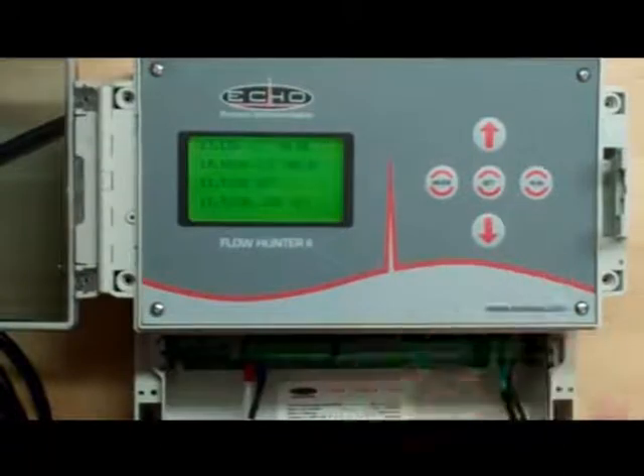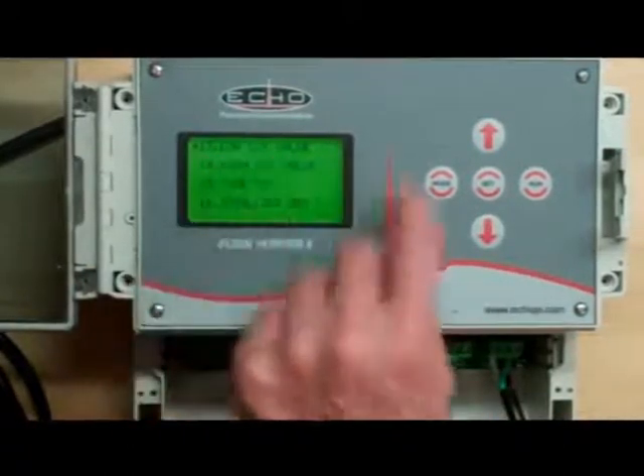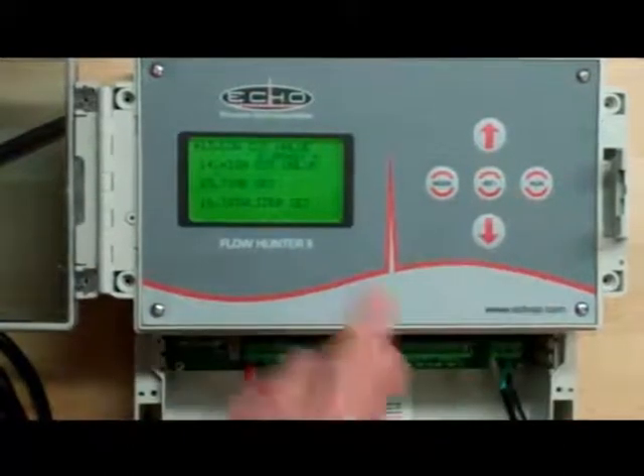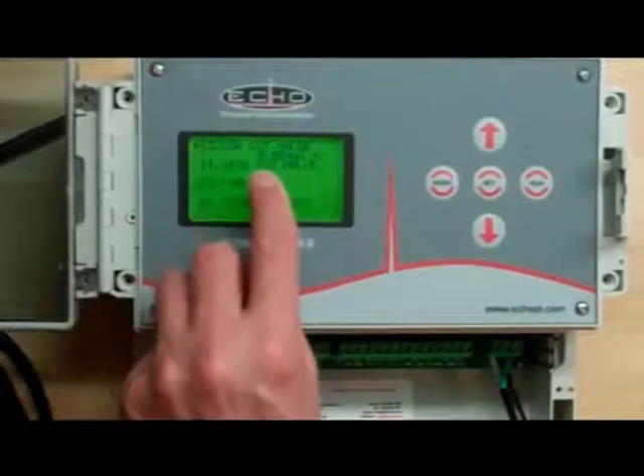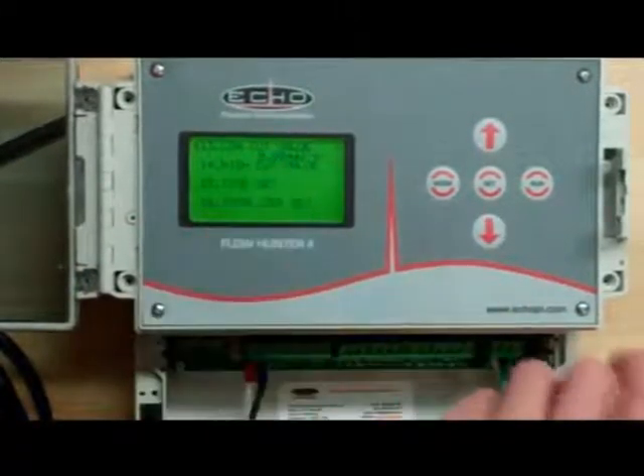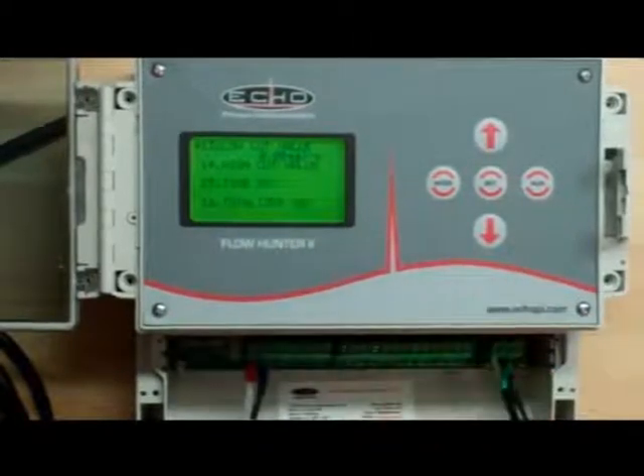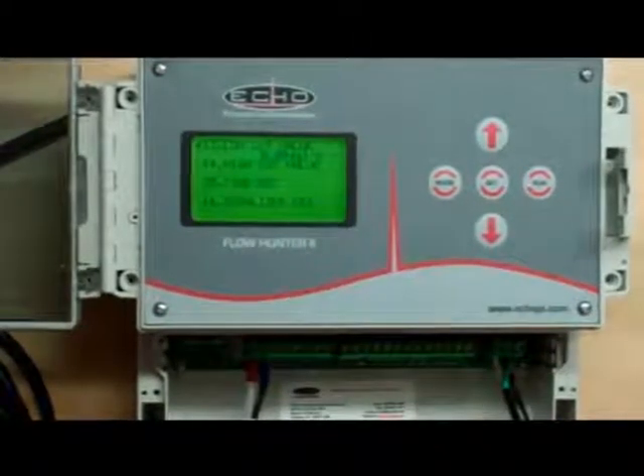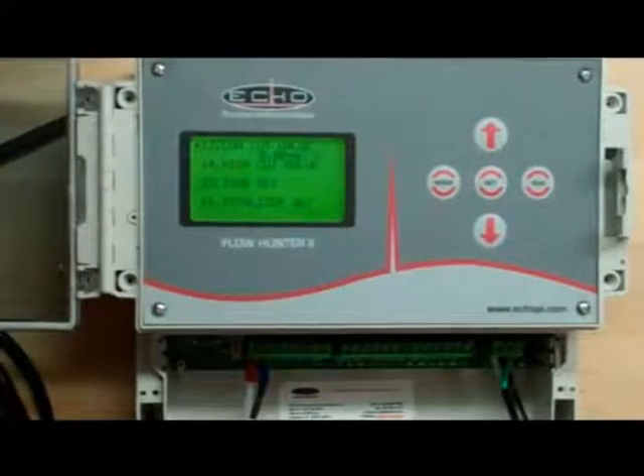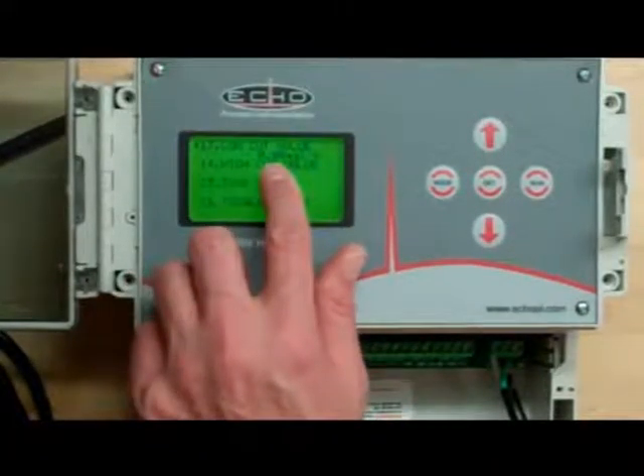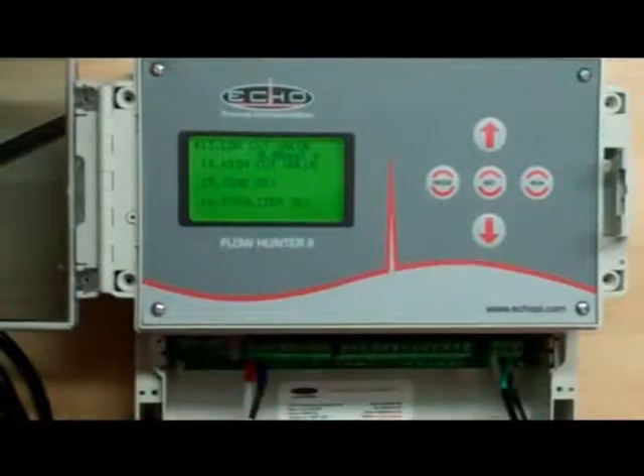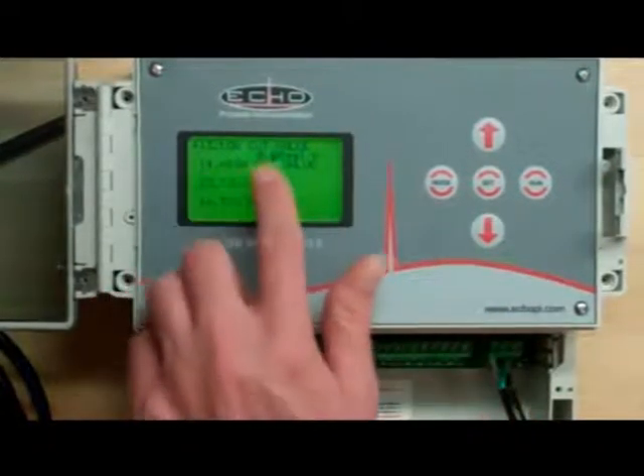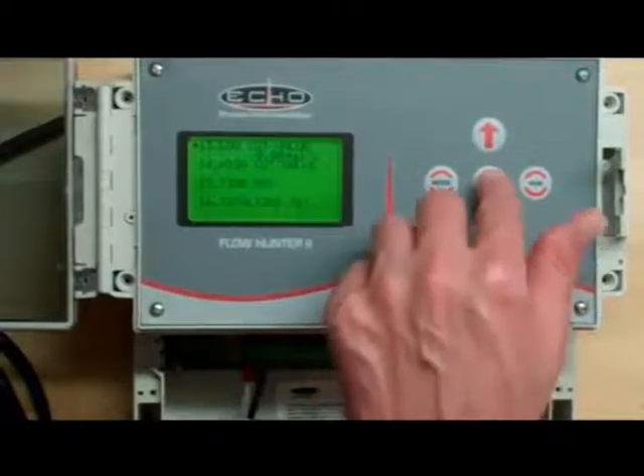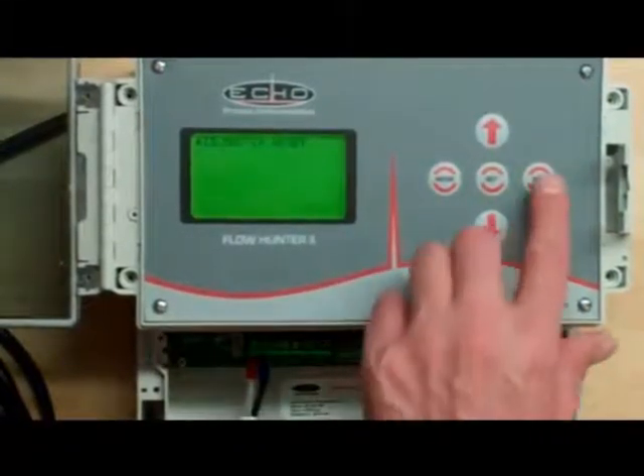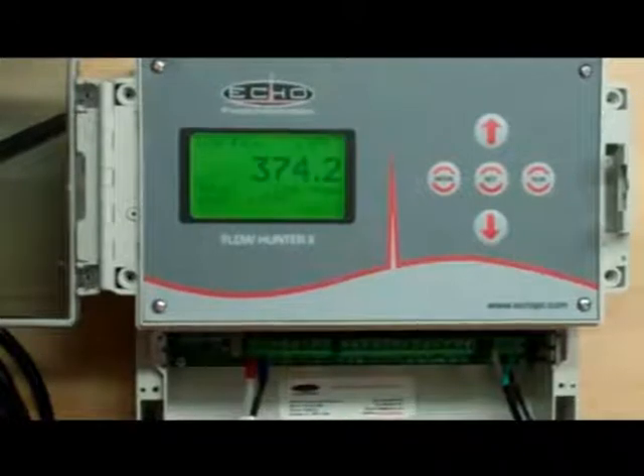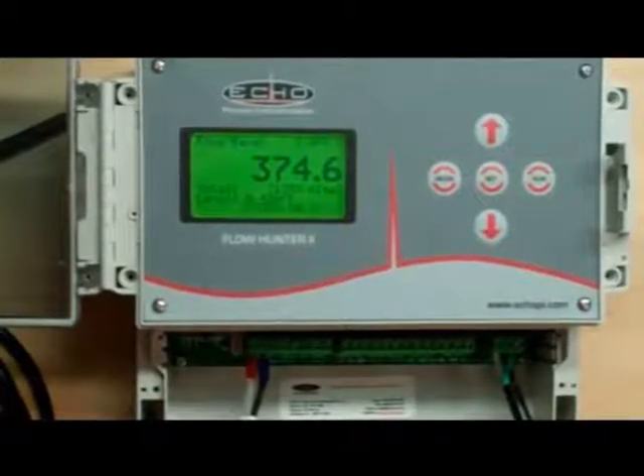We're going to go down to number 13, which is your low flow cut value. We hit set to enter. Here, if you want to show true 0 flow, you set this to 0 and then hit set. Now if you get a trickle and you do not want to calculate the trickle and you want to ignore it, you would set this up a little bit to whatever gallons per minute that you do not want to see on your low end. After you have that set, hit set. After you're done here, you hit run mode, and this is going to take us back to start.